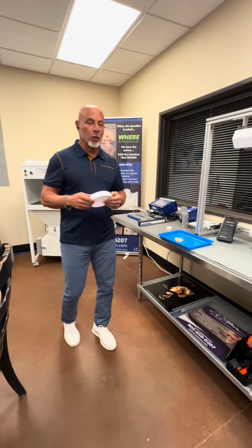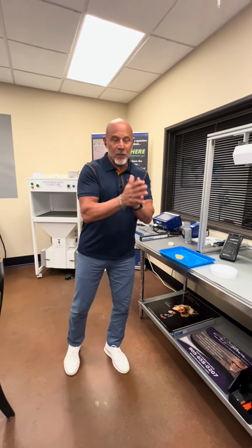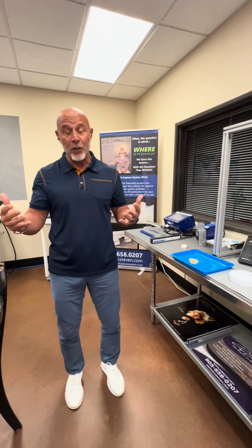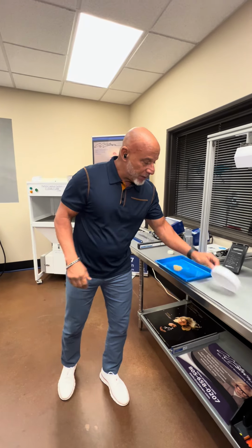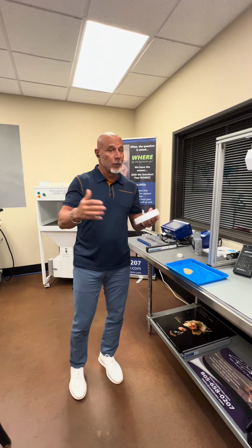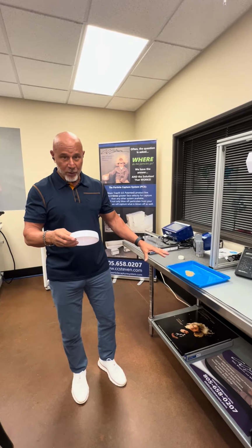So let's summarize real quick. Again, contact and separation of a plastic part is what's generating our high electrostatic fields, that ESA. That electrostatic attraction is going to happen to any plastic part anywhere from 2 kilovolts, 2,000 volts and up, to attract a particulate to it.